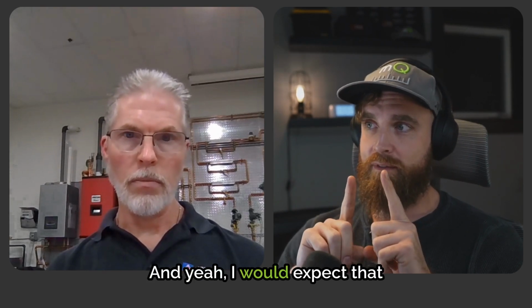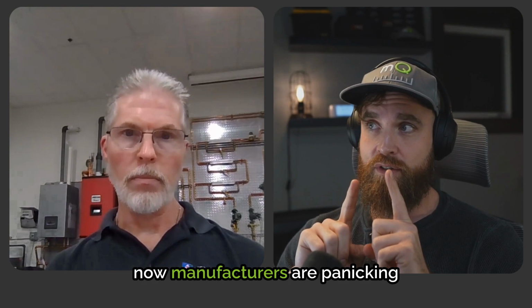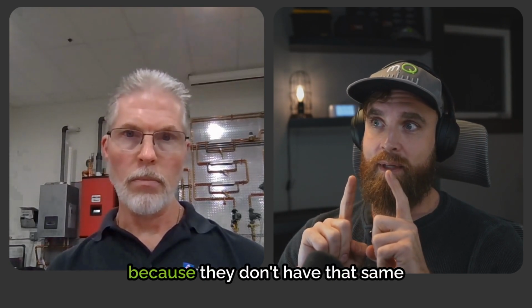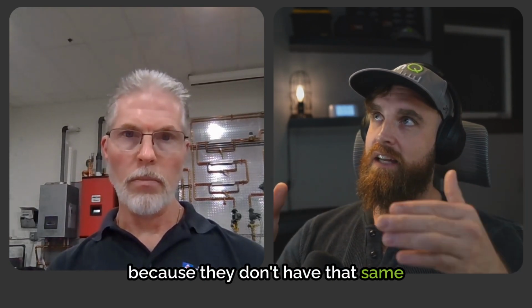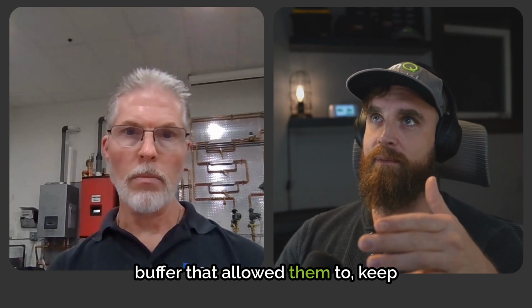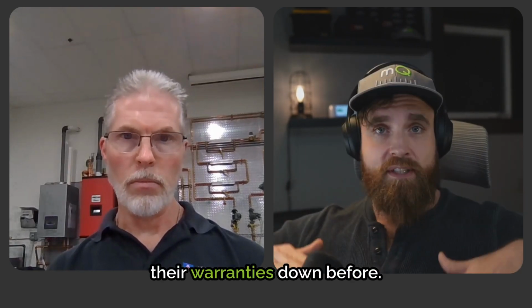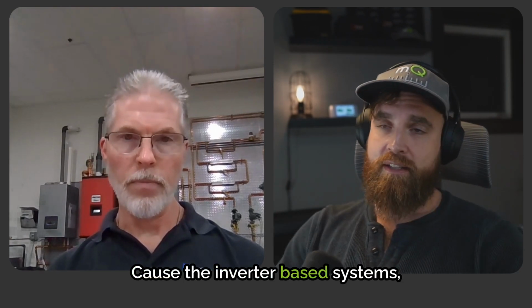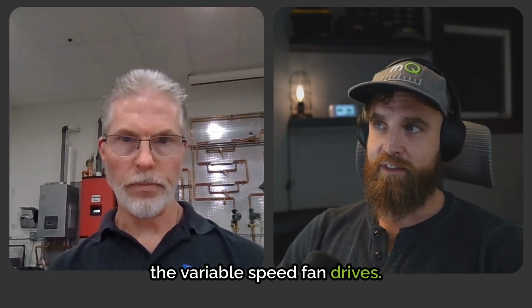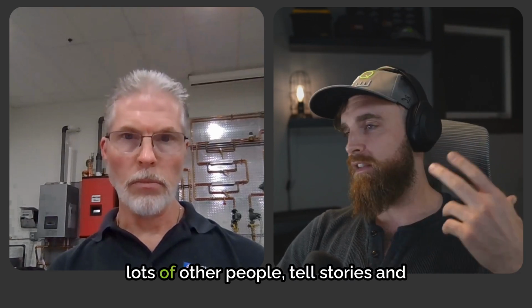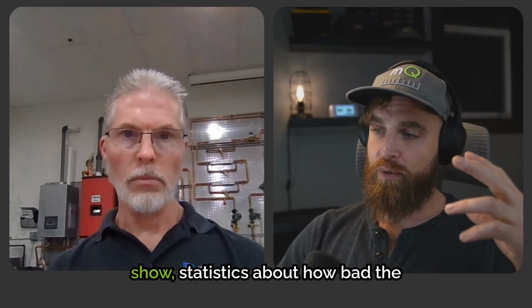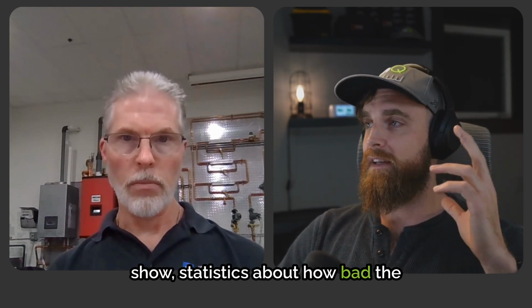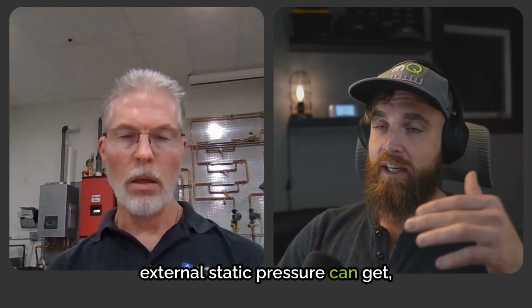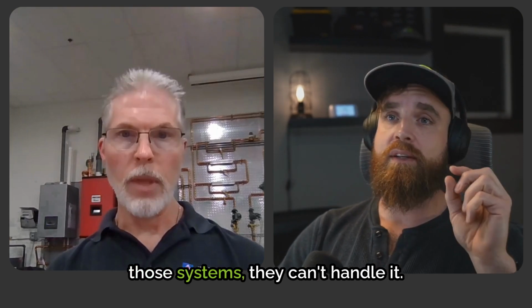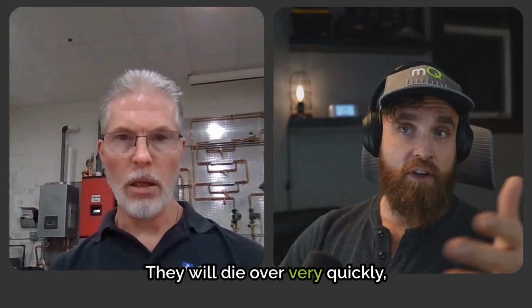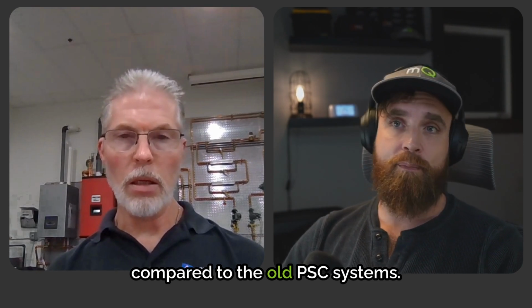And yeah, I would expect that now manufacturers are panicking, because they don't have that same buffer that allowed them to keep their warranties down before. Because the inverter-based systems, the variable speed fan drives - I've heard Nate Adams, yourself, lots of other people tell stories and show statistics about how bad the external static pressure can get, well, on any system, but with those systems they can't handle it. They will die over very quickly compared to the old PSC systems.